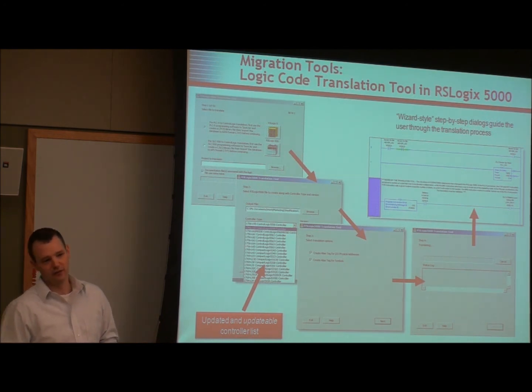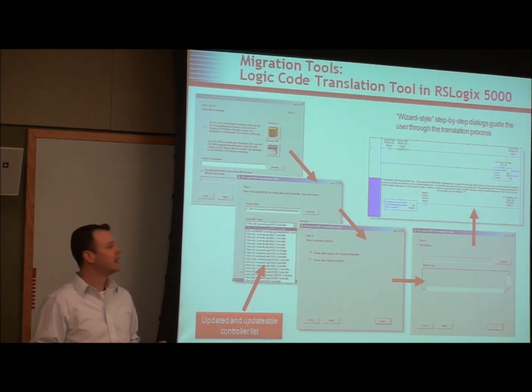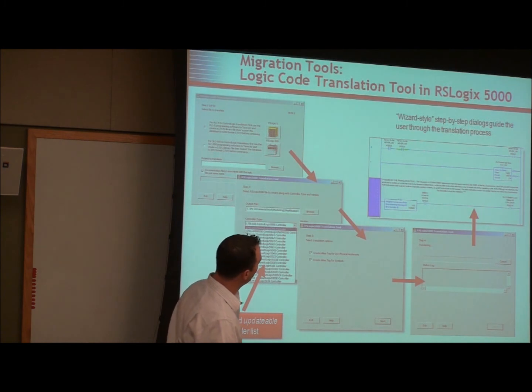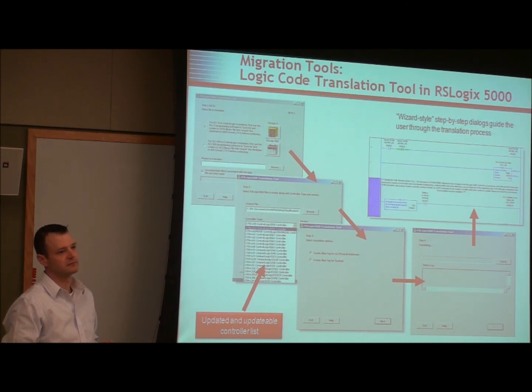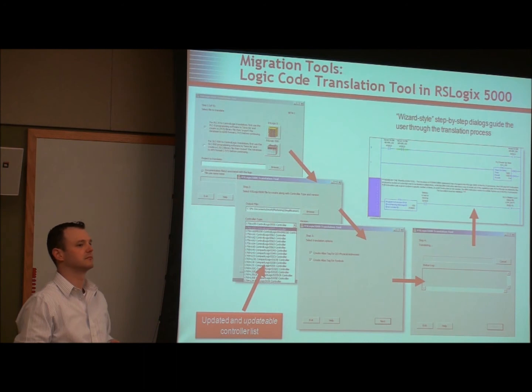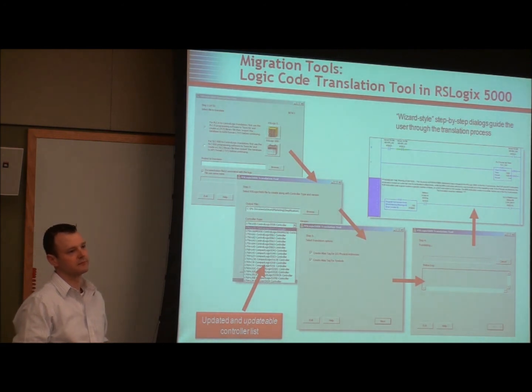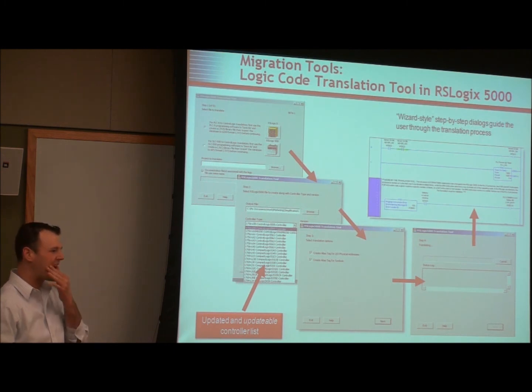I recommend doing a full test and validation of the system to make sure everything is performing as desired before putting it into production. The conversion tool will get you at least 95% of the way there and save you a lot of labor. One more thought: if you're going from an SLC to one of these new processors and some functionality of your SLC system was dependent on scan time — and there are applications like that — all of a sudden your scan time goes from a Yugo to a Lamborghini, and there could potentially be issues there.